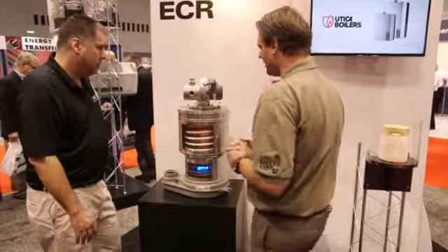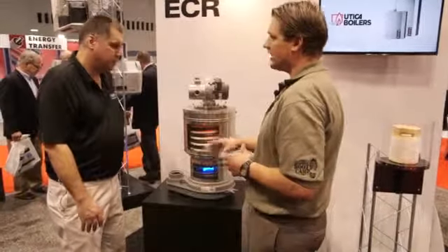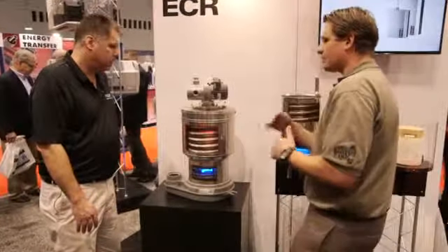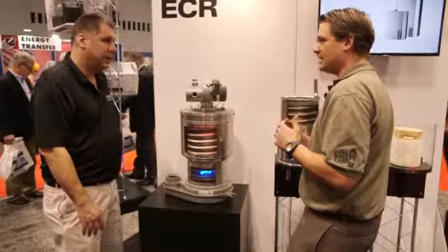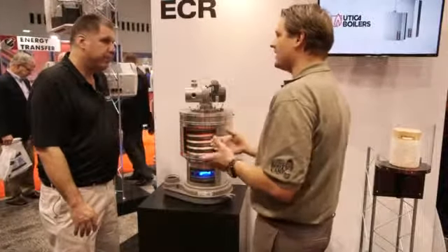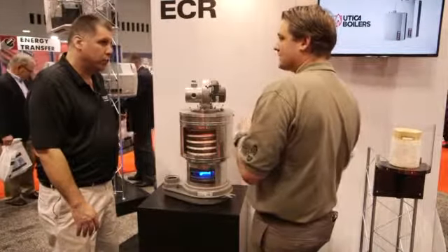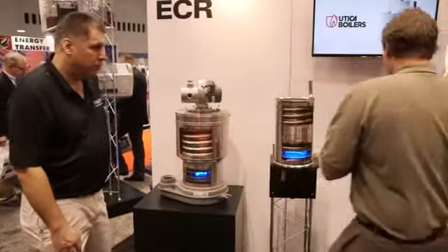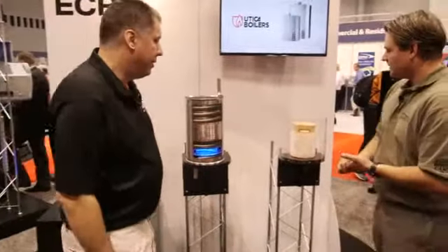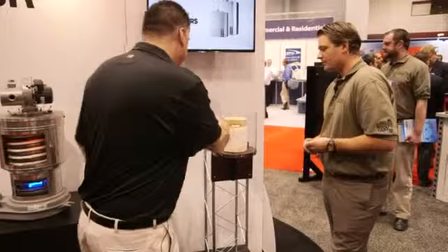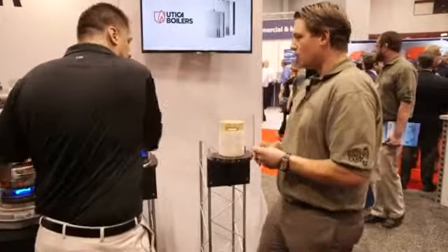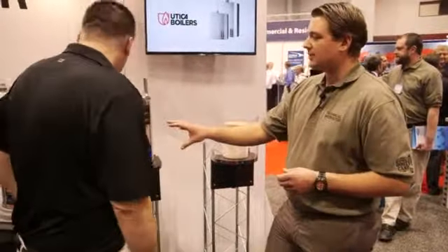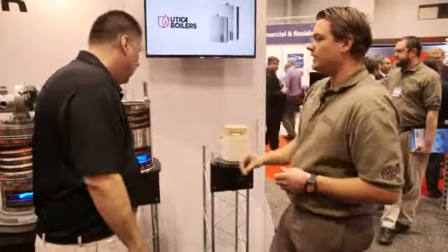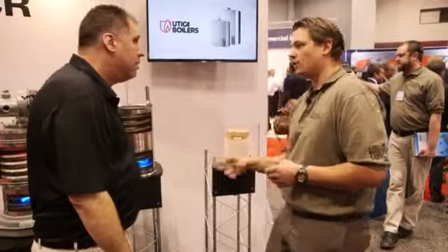The other thing that we've done in here is when they were developing this, they changed the refractory inside of it to help disperse the heat across the fins evenly. I see. When they did that, they decided, well, let's use that in all our products. It's actually a patent pending design. That's what we have over here. Interesting. This is our new refractory. And that's used on both these heat exchangers, or just on the commercial? Both of them. Once they developed it in the larger, the 299 boiler, they decided to implement it in the smaller units to help out with that.